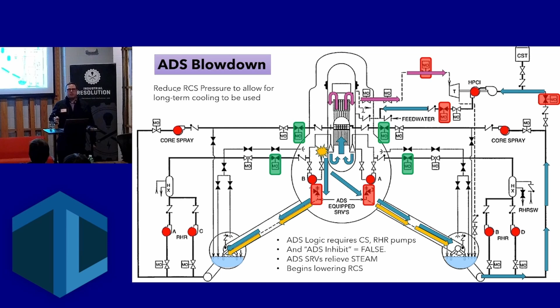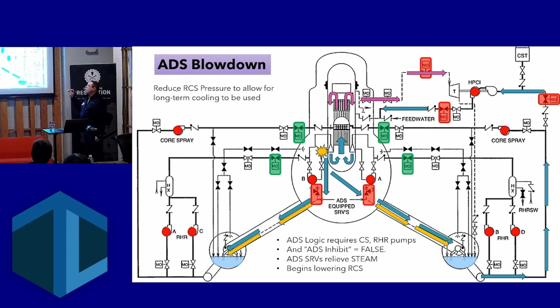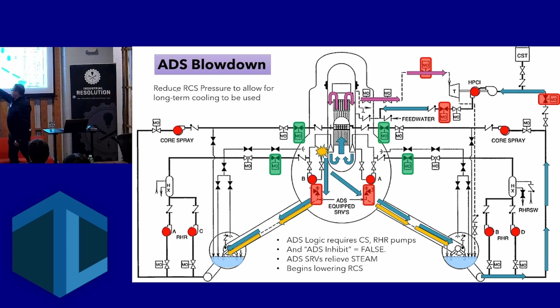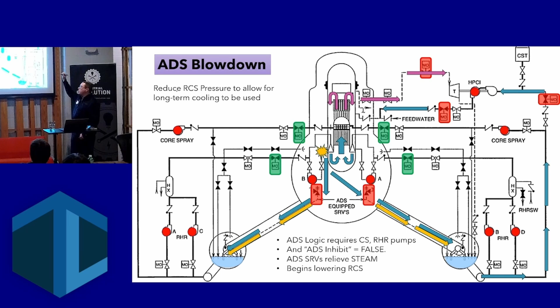It's a saturated system thermodynamically, so if you remember anything from physics class, this means that pressure and temperature follow each other. If I lower pressure, I can lower temperature in the plant, and if I lower temperature, I can lower pressure in the plant. And this works beautifully, synergistically, to help us provide some cooling now by blowing all this steam into the torus, right? You can see little downcomer regions here, where the steam is now going to condense, creates a vacuum, and lowers pressure in containment while we're trying to get the system down to where LPCI, the low pressure coolant injection system, can inject.